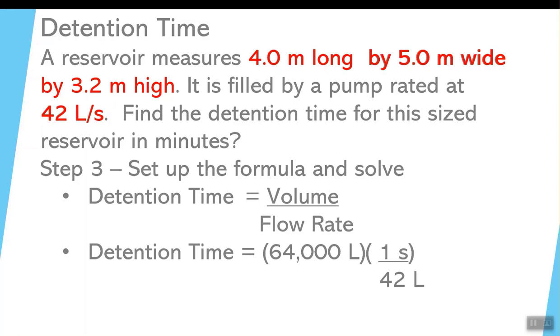So 64,000 liters divided by 42 liters. Notice the units cancel out. And look what's left on the top. What unit didn't get canceled out? Seconds. And that is a unit for time, so that's a good sign. That detention time is calculated out to be 1,523.8 seconds.